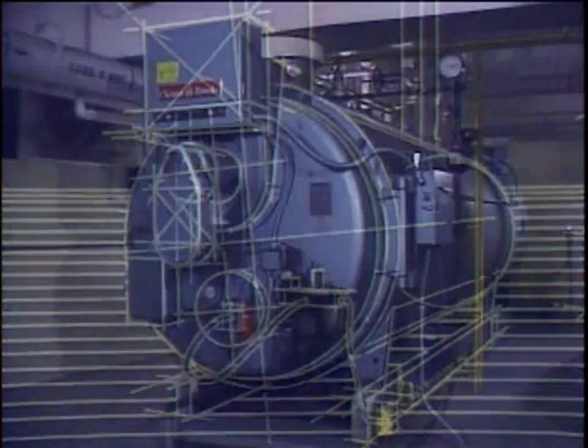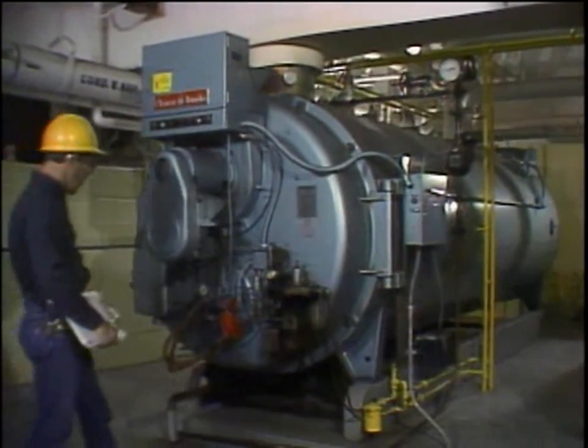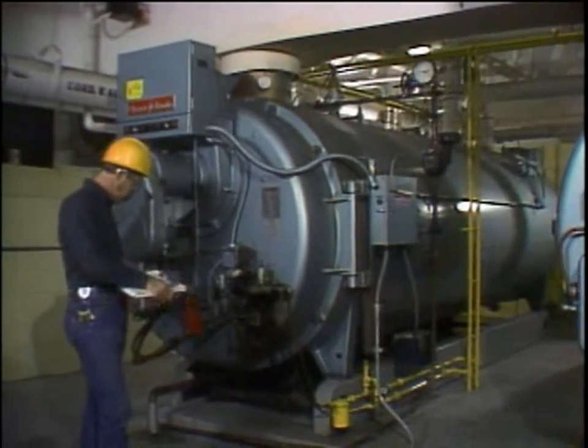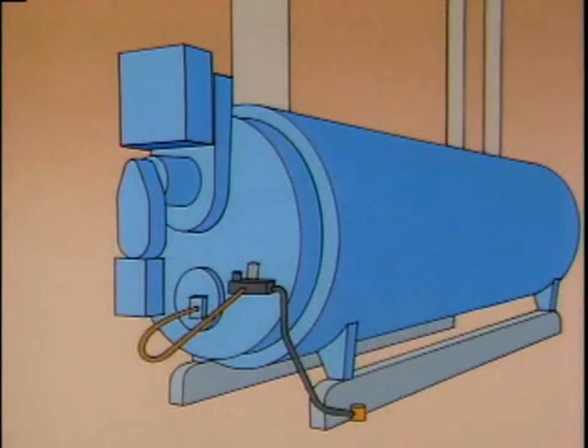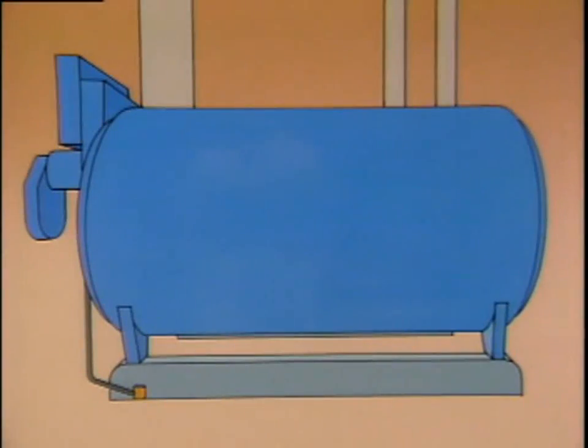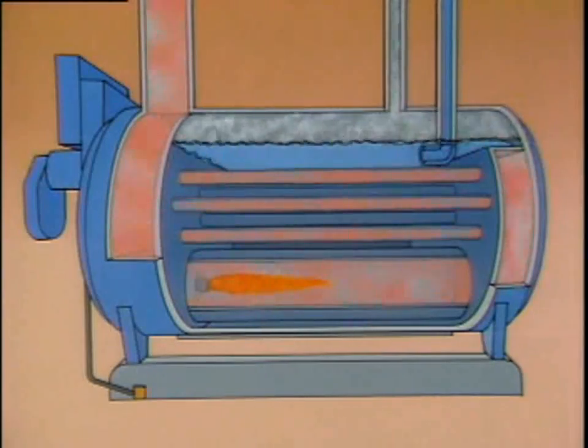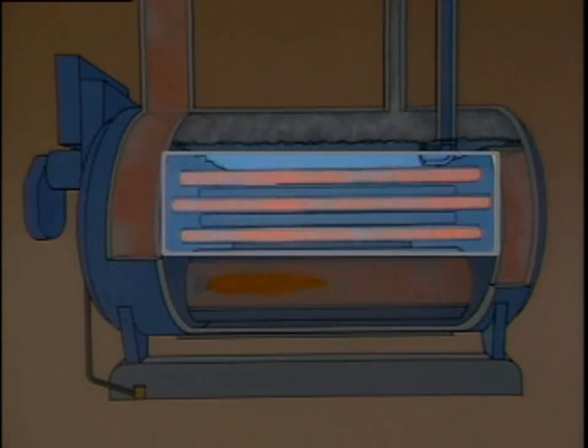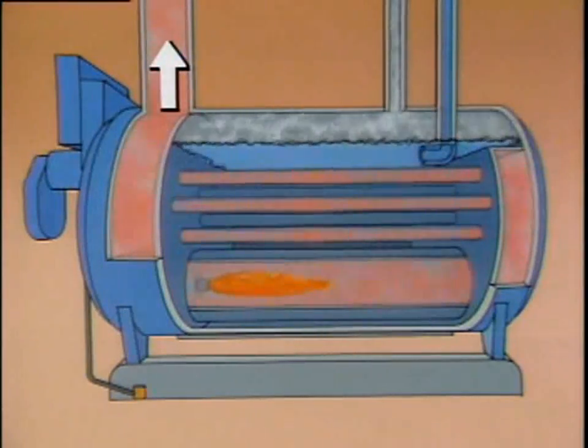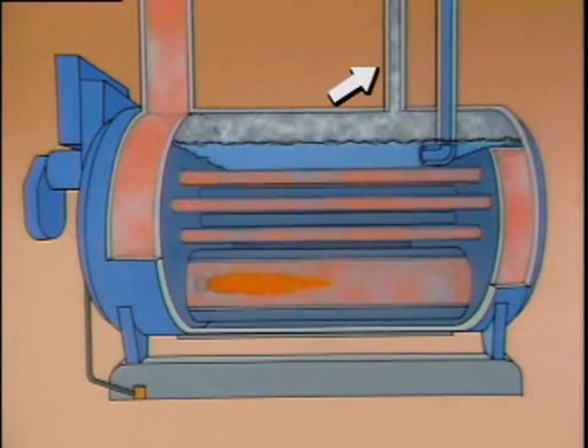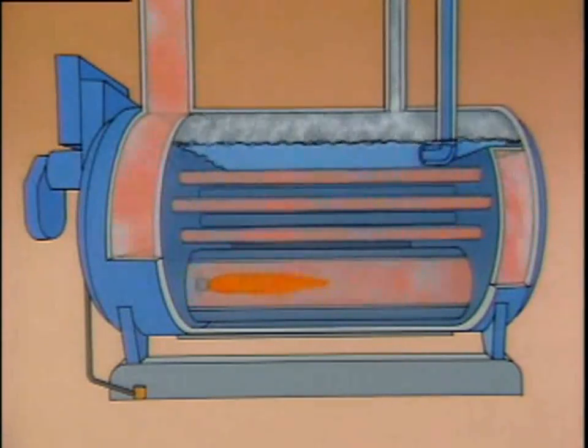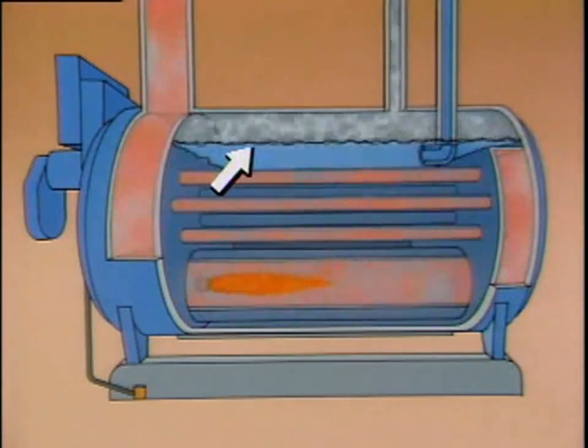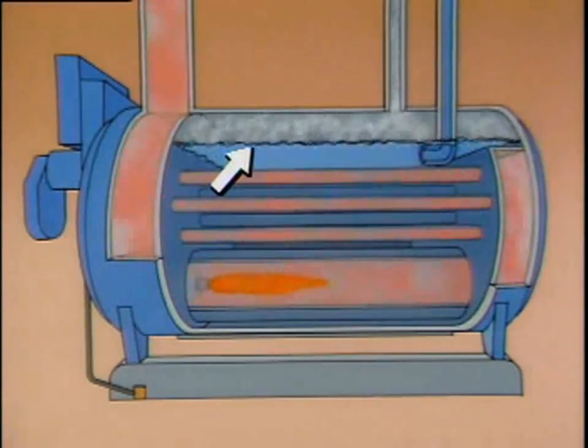Fire tube boilers route hot combustion gases through metal tubes. The tubes run through a shell filled with water. Fire tube boilers vary in design, but most operate under similar principles. The combustion area is at one end, and a group of horizontal fire tubes routes combustion gases through the boiler. There's also an outlet for the gases, a feed water line, and a steam outlet line. During operation, water enters through the feed water line, and the water level is maintained above the fire tubes to protect them from overheating.